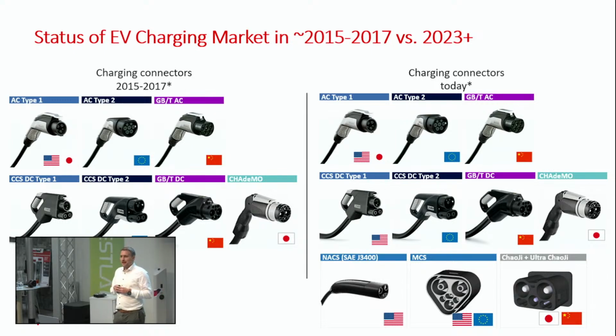Basically, at the end of the day, it's a new connector, with no change in protocol so far. In the middle, you see the MCS connector, megawatt charging system, which we had in the previous presentation already. That is the standard addressing new high power and heavy duty applications, going up to 3,000 amps maximum specification and 1,250 volts, in total making 3.75 megawatts.